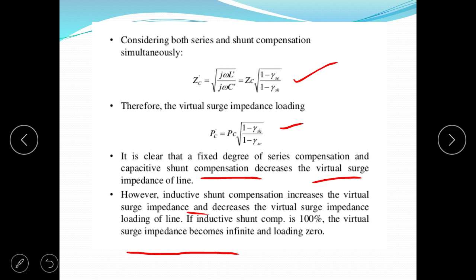Now suppose we want a flat voltage profile corresponding to 1.2 PC without shunt compensation. So series compensation required will be PC dash is equal to PC divided by root 1 minus gamma SE. That is 1.2 into PC, that is PC root 1 minus gamma SE. So gamma SE is equal to 0.306 per unit. That is known as the series compensation factor. Now assume series compensation to be 0. The shunt compensation required corresponding to 1.2 PC means to increase power transfer capability of the line up to 20%. So PC dash is equal to PC root 1 minus gamma SH. So we obtain gamma SH is equal to minus 0.44 per unit.